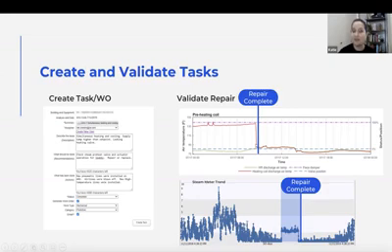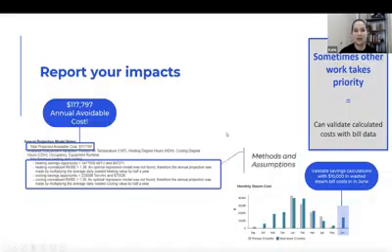And in this case, because the problem was ongoing and did happen for a long time, you can see it in the meter. This is what I really wanted to talk about when we talk about energy savings and how to quantify it. When you look at the steam meter, this is interval data for your steam consumption for an entire year. You see when the problem started to happen, and you see when it was repaired.